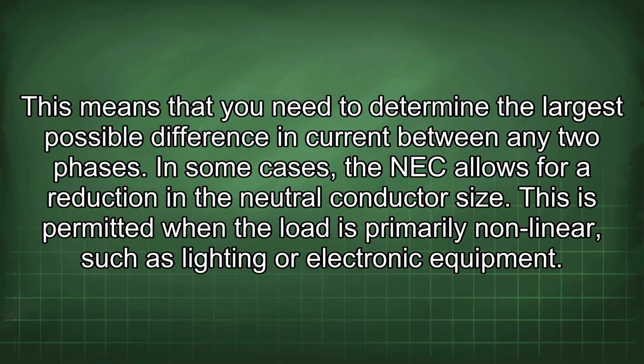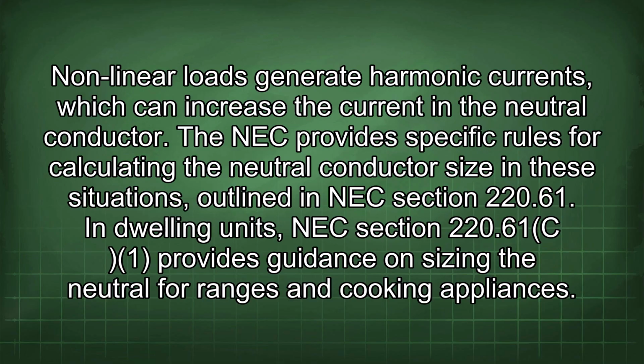This is permitted when the load is primarily nonlinear, such as lighting or electronic equipment. Nonlinear loads generate harmonic currents, which can increase the current in the neutral conductor. The NEC provides specific rules for calculating the neutral conductor size in these situations, outlined in NEC section 220.61. In dwelling units, NEC section 220.61 provides guidance on sizing the neutral for ranges and cooking appliances.